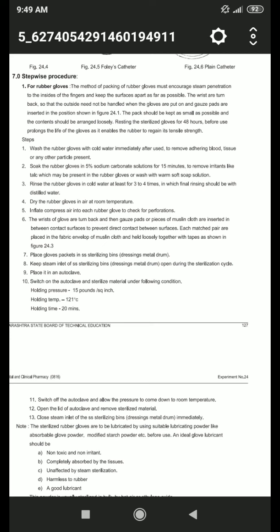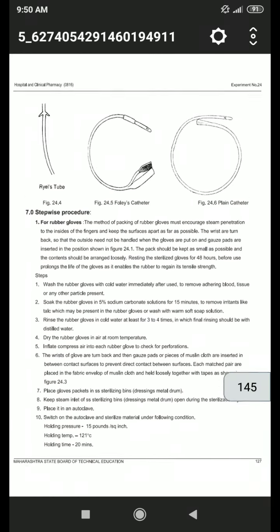Then dry the rubber gloves in air at room temperature. Then inflate compressed air into each rubber glove to check for perforations. Then the wrists of the gloves are turned back, and gauze pads or pieces of muslin cloth are inserted between the contact surfaces to prevent direct contact between the surfaces. Then each matching pair is placed in a fabric envelope of muslin cloth and held loosely together with tapes, as shown in figure 24.3.